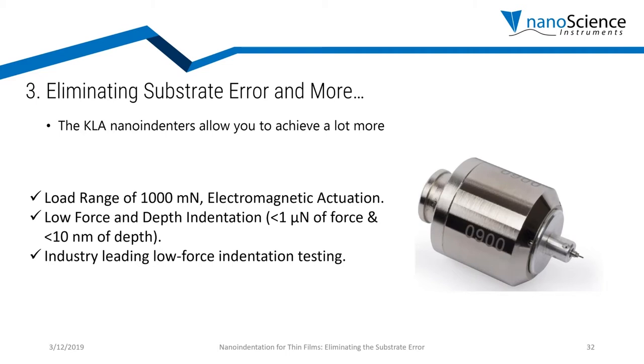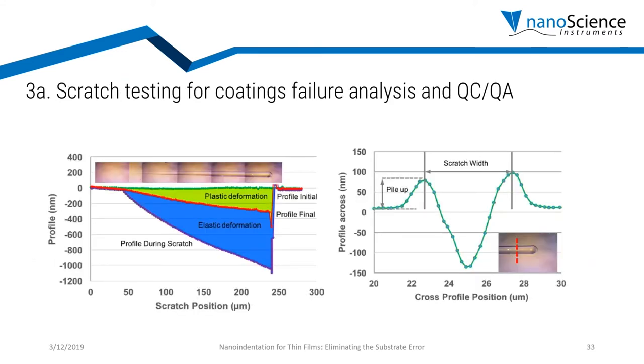Beyond eliminating the substrate error, there are other property measurements you can perform with the same system, such as scratch testing and high temperature testing. This is possible because our products apply a really large load range while still maintaining force and depth resolution. In some other commercial indenters, high load resolution comes at the expense of depth resolution. Because our system is linear with decoupled channels, we can maintain resolution in both simultaneously.